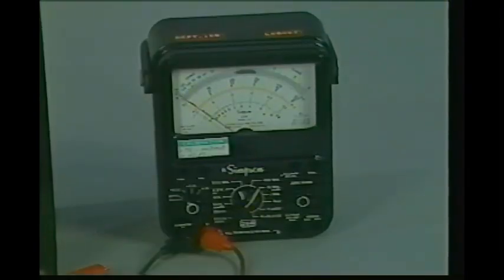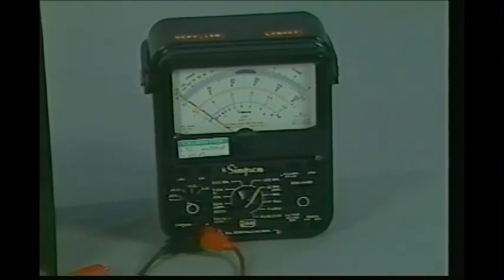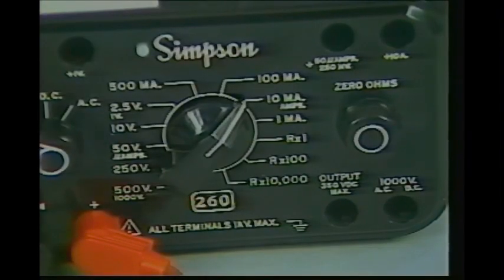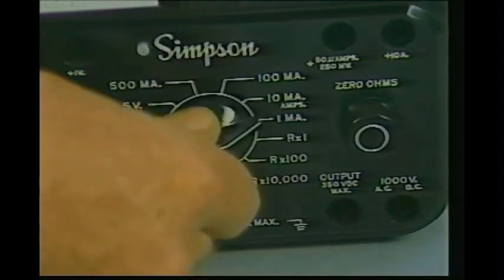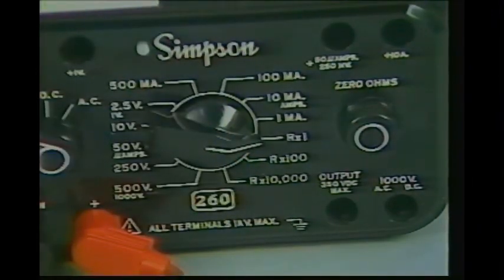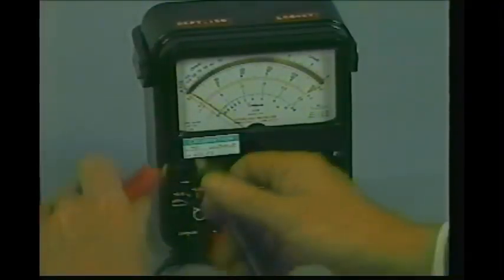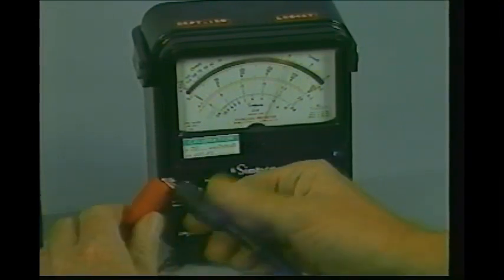To make a field test of the rectifier assembly, you'll need an analog meter. The analog meter has an R times one scale. This scale is used for testing diodes. The first step is to set the meter on the R times one scale. Short the meter leads together and zero the meter.